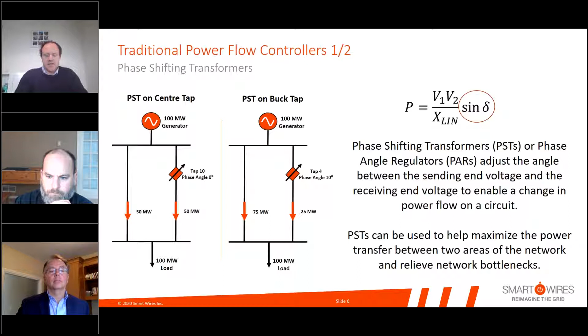Now you can see physically what PSTs look like here, but they're custom built devices for specific needs. So for example, if you need a PST to connect 2 areas with a 40-degree angle separation on a 1000 MVA rated line, you buy and procure that PST for that specific application. So it makes them very custom built and used for very bespoke applications. It typically takes 2 to 3 years to manufacture, deliver to site and commission a PST. They're an extremely good solution for connecting 2 areas with large geographic or electrical separation, basically areas with large angular separation.